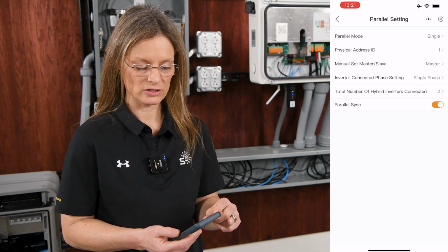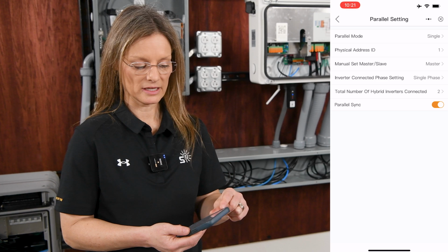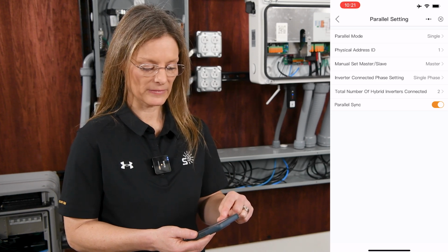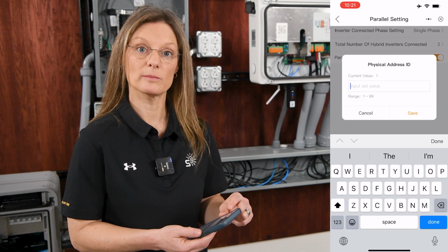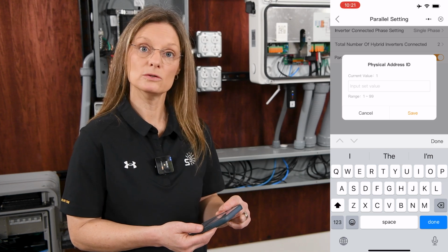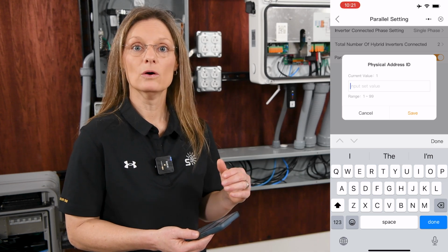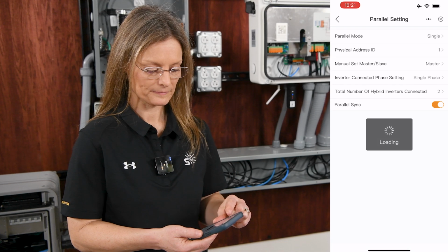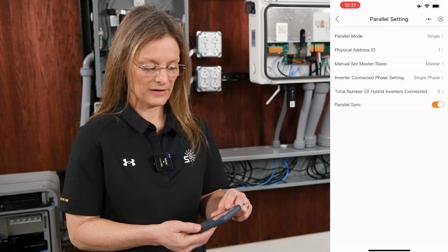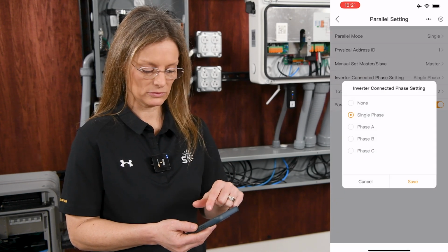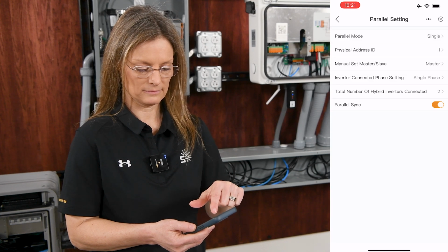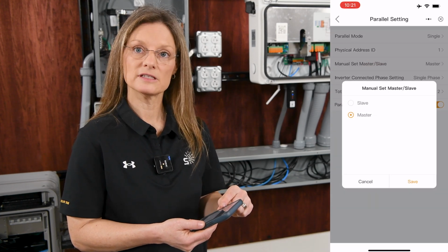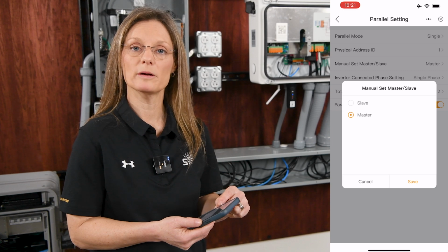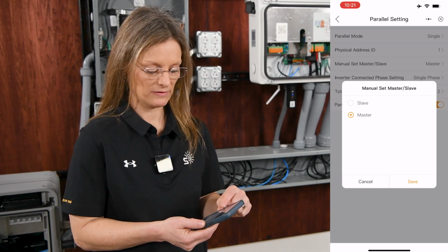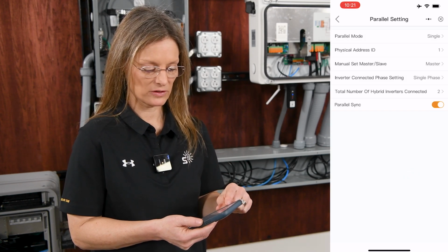So once that's set on my master, I would connect to each of my inverters and go through and select that each of them are in parallel mode. I would change the physical address for my second inverter to say 2, or for my third inverter to say 3, or on down the line. We would save each one of those. If it's not my master, I would set each of those to be slave instead of master, because I'm only going to have one master, and that is my number 1 inverter, and we would save that setting for each of those.